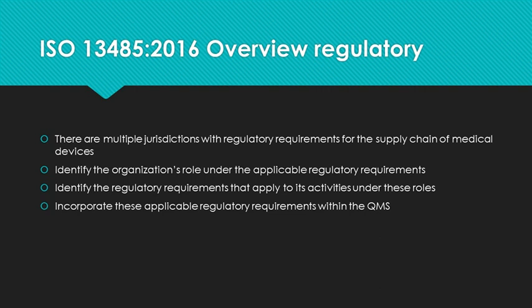Companies implementing ISO 13485 are expected to identify the regulatory requirements that apply to its activities under these roles. So does the company have the responsibility and authority to recall product? And what documentation is needed to be kept, and for how long? A company implementing ISO 13485 is expected to incorporate the applicable regulatory requirements within the QMS, which means there should be procedures for reporting to regulatory authorities and/or their customers, and there should be implemented procedures for traceability.